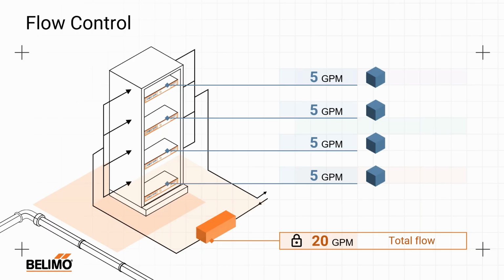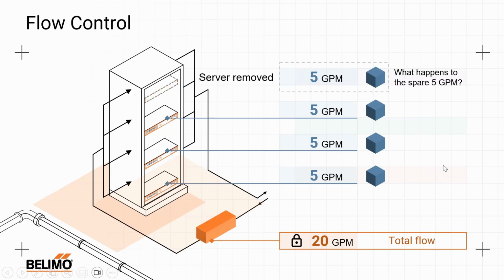Now I'm fixing my flow at 20 gallons a minute. So we have the little lock showing up next to my 20 gallons a minute, indicating that that is fixed. So then the question begs itself, if I have 20 gallons a minute and it's fixed, what happens if I need to remove one of the servers? So let's say I have to do service on the server or replace it with a new one for some reason or another. I pull that server out, there's still 20 gallons a minute going into that rack. What happens to that 5 gallons a minute?